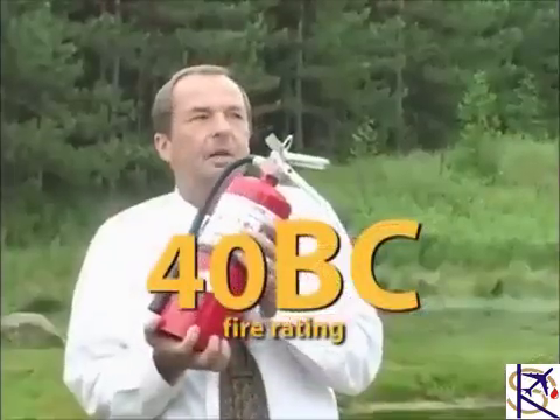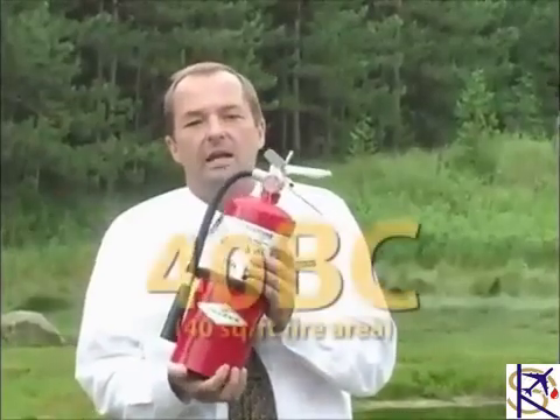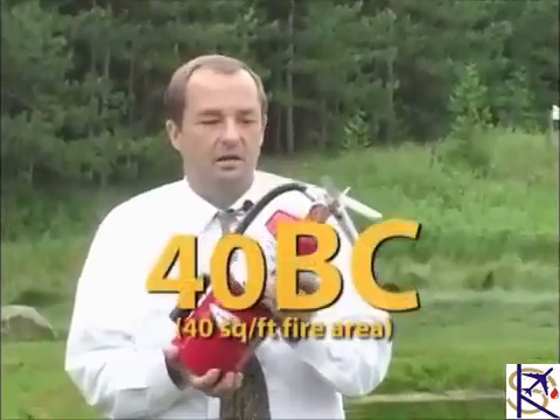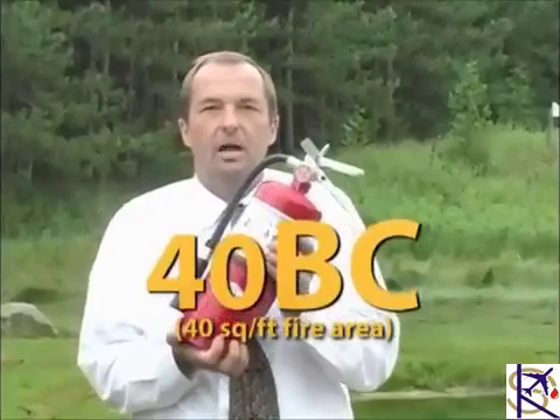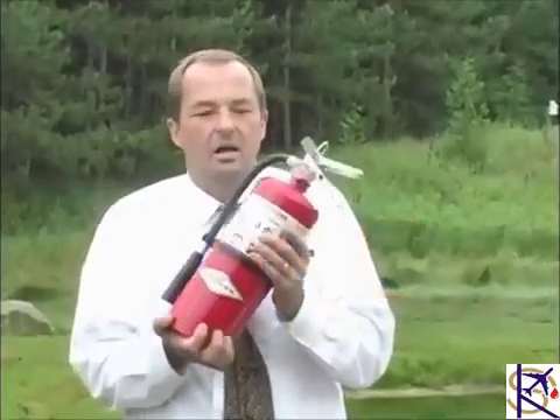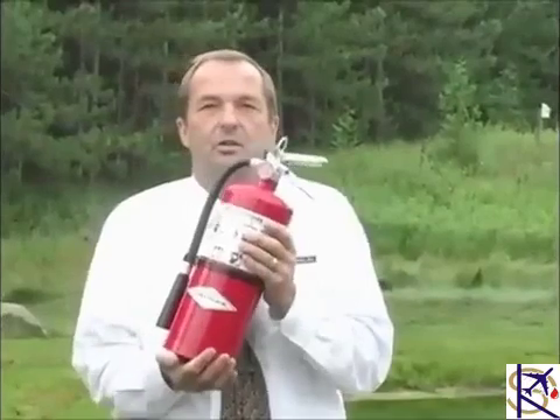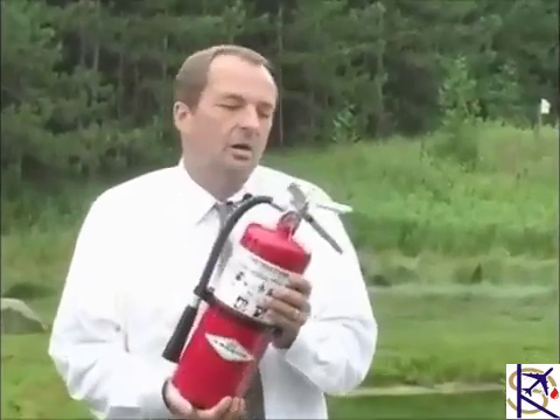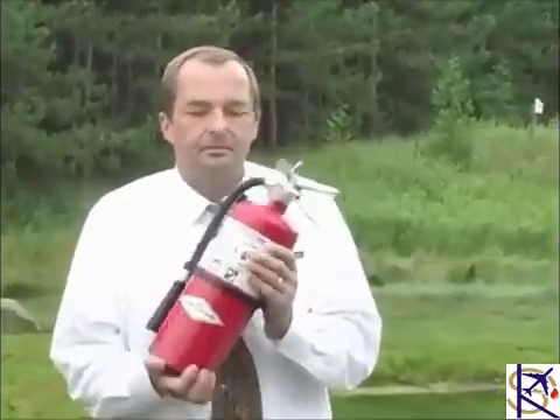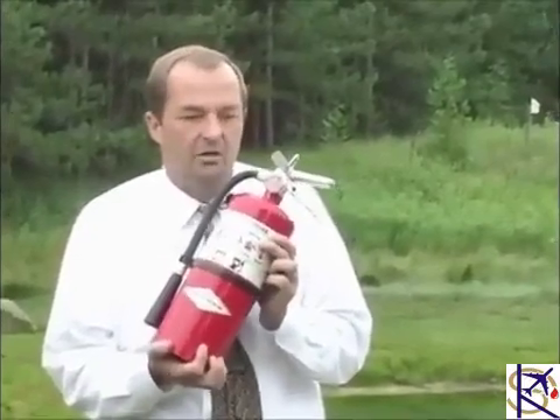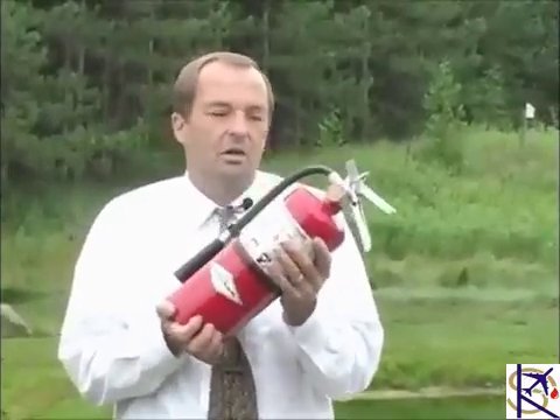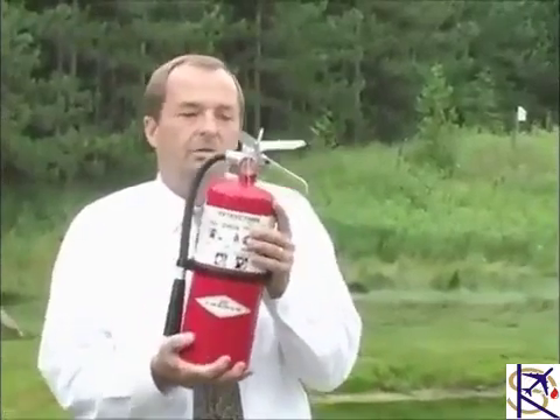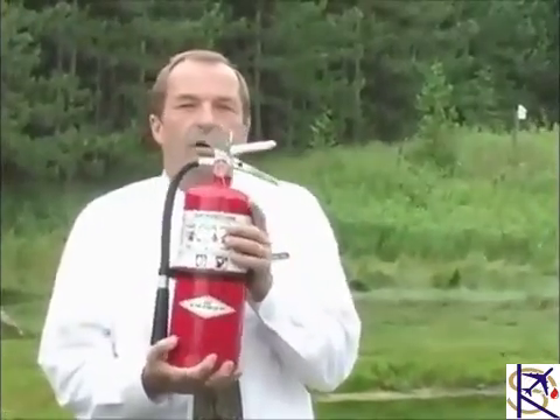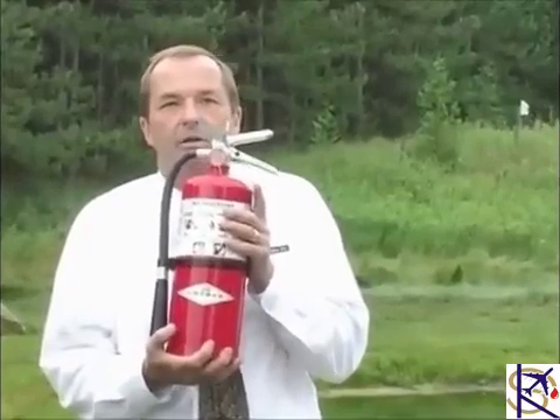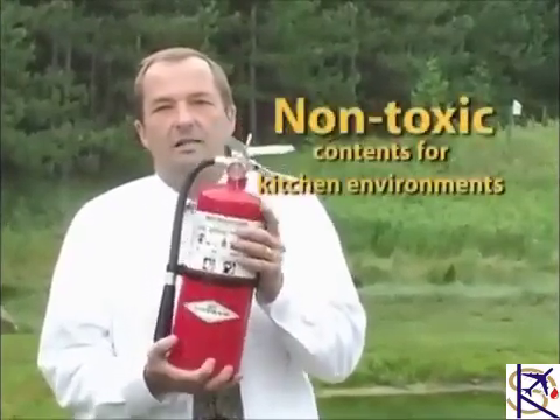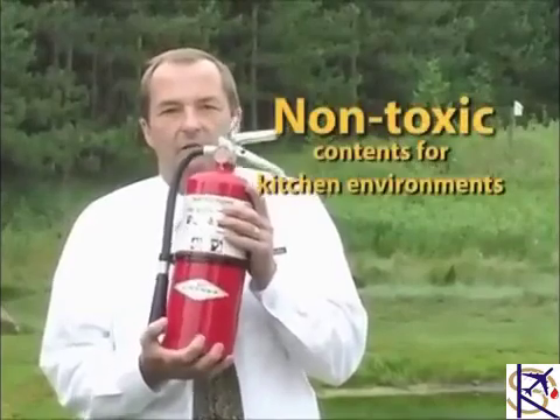And the number 40 is the amount of square feet of oil and electrical fire this extinguisher will put out for an average person using it. So 40 square feet of fire area, which is fairly large. It will put out a substantial fire, but it is primarily used in kitchens, where the regular powder, bicarbonate of soda, is not toxic to the kitchen and food area.